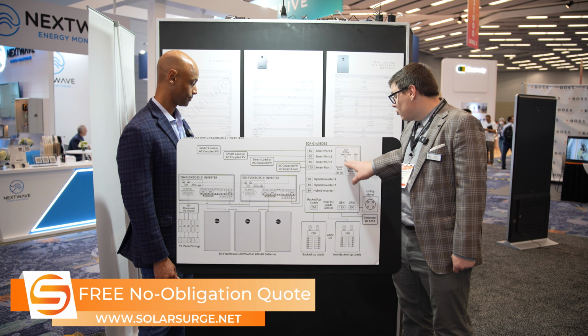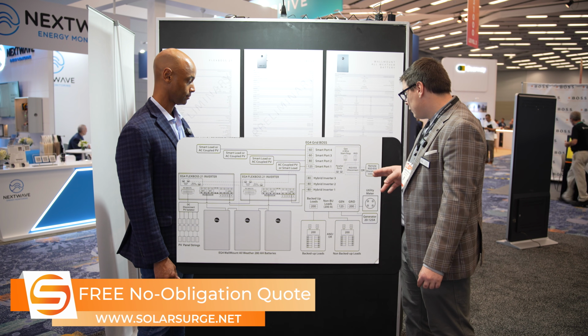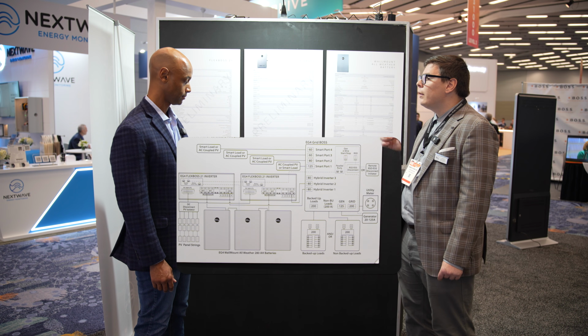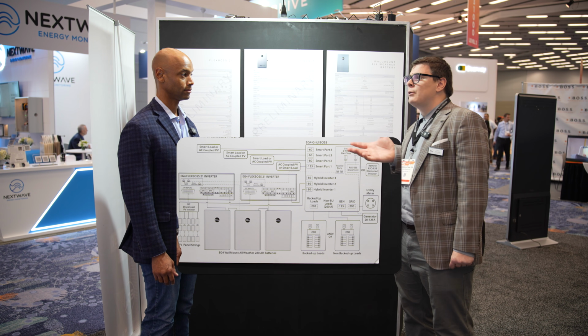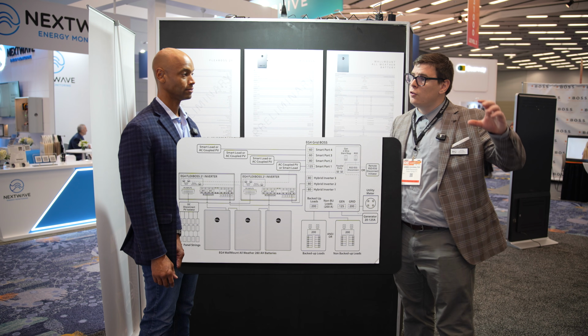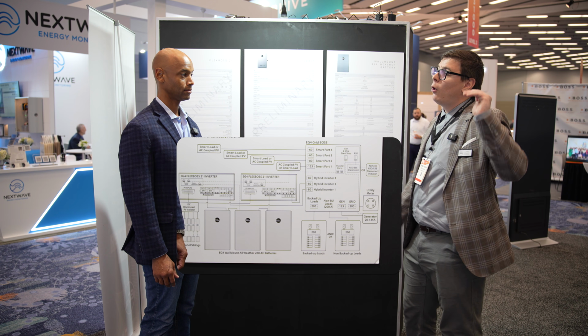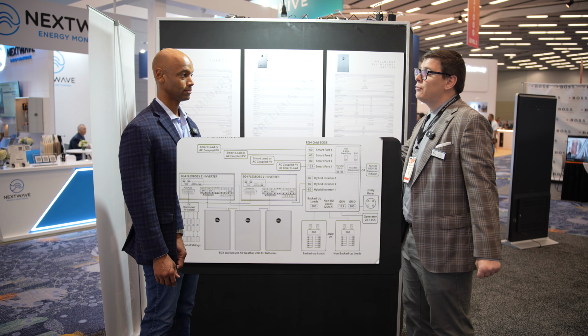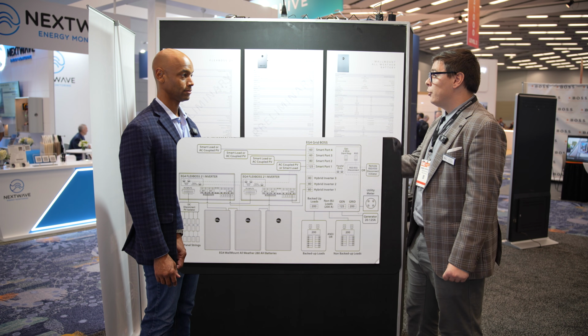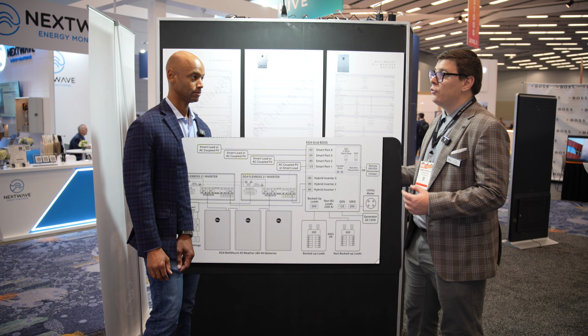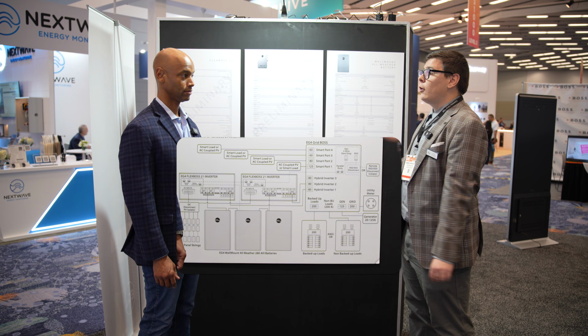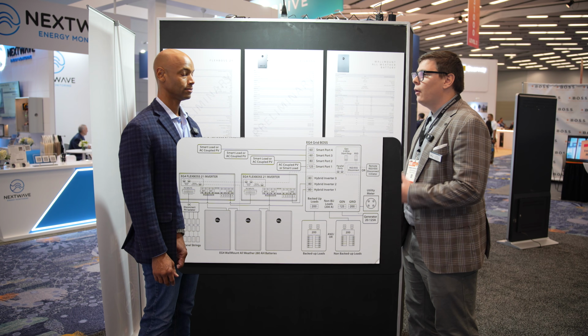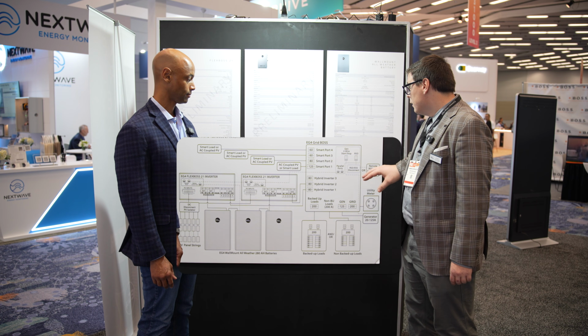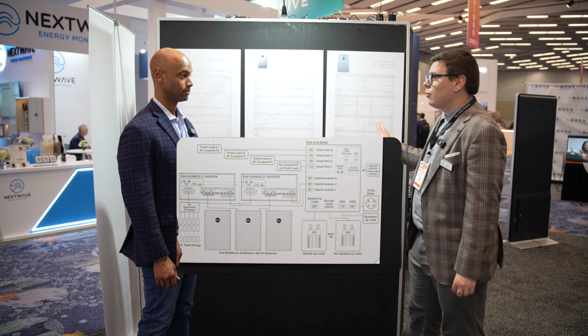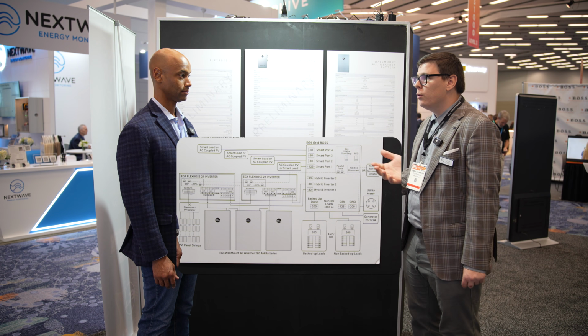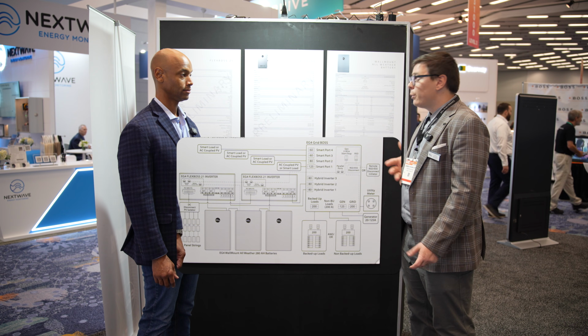We've got that covered. We've got a 2-wire start-stop at the GridBoss now. We have the rapid shutdown. I think another point we didn't really make is that our system has total rapid shutdown. So we are the first ESS provider that didn't just cut the power at the inverter, but also every breaker on our battery trips if the fireman hits the switch. We were in New York with the New York Fire Department explaining this and some of the enhanced standards we try to build our products to. They were asking questions about how to keep ESSs safe, and this is one thing that we did. So the rapid shutdown works like a regular rapid shutdown, but it also trips all the battery breakers. You've got new NEC codes that we think are headed that direction. We think we got there ahead of time.